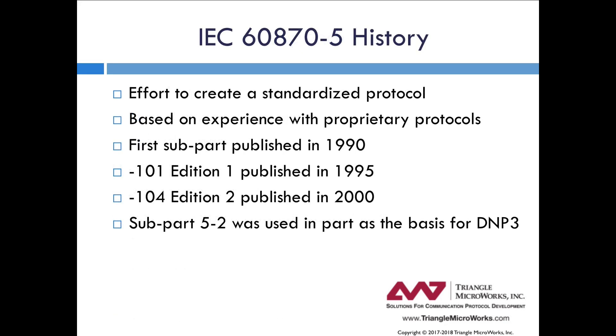Let's start with a quick history of 60870-5. This protocol goes way back to the early 1990s, when they started working on standardizing a protocol for telecontrol and SCADA systems. The first subpart was published in 1990, and the original subparts talked mostly about the lower level layers. Finally in 1995, the 101 spec came into being, leveraging all of the original subparts. In 2000, the 104 spec was introduced, which is very similar to 101 but focused more on TCP/IP applications, whereas 101 is serial. DNP is also based in part on the 60870-5 subparts, so it is somewhat similar, and throughout this presentation we'll point out some of the major differences between the two standards.